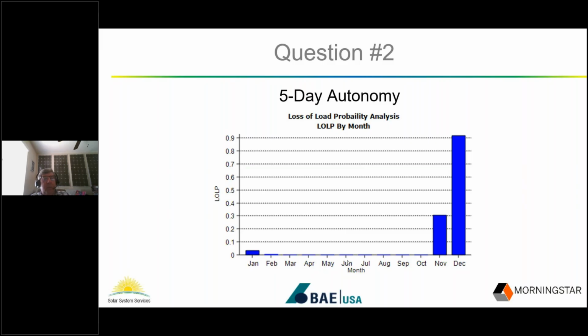However, some industries like railroad and oil and gas need even better than that — 99.99% availability. In those cases, they use 7-day and 8-day batteries, which is also what IEEE 1562 recommends, specifying 7-day batteries as a minimum for critical loads.